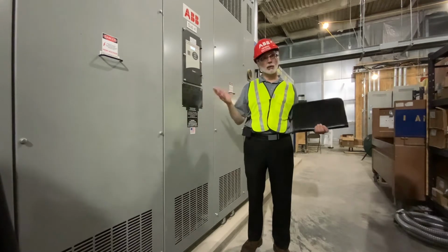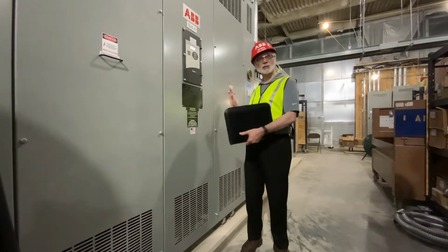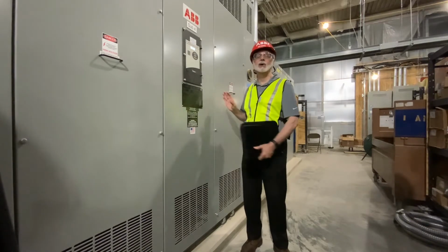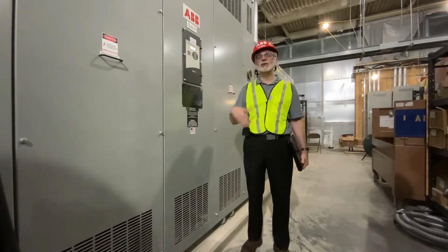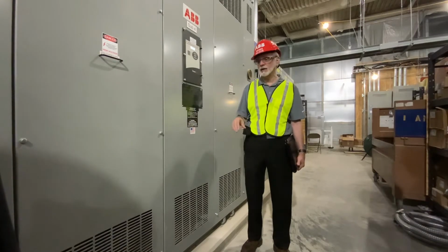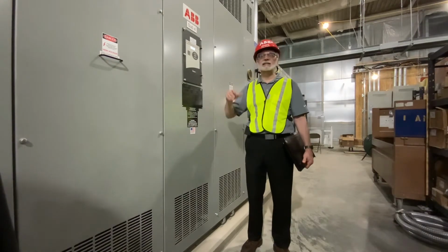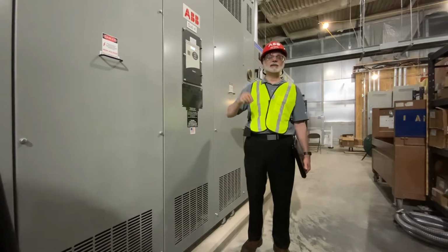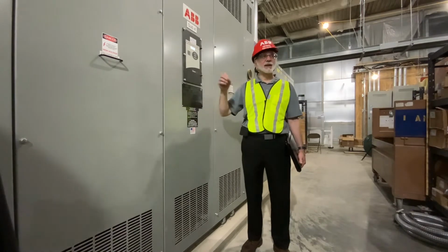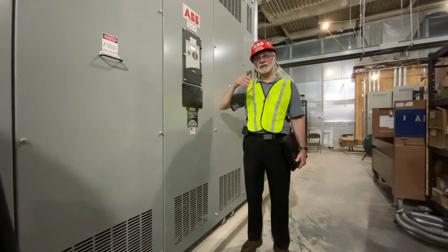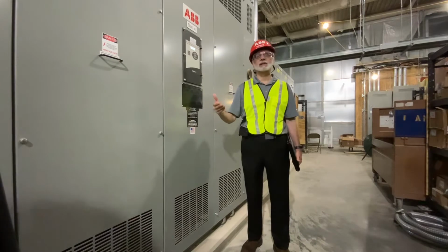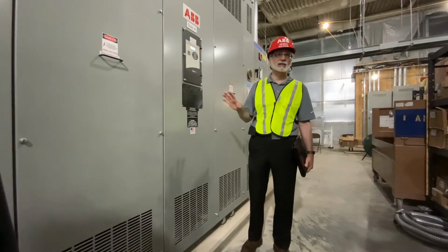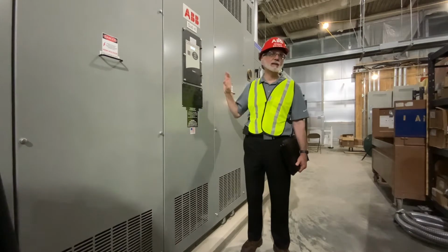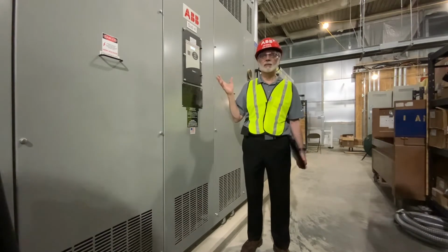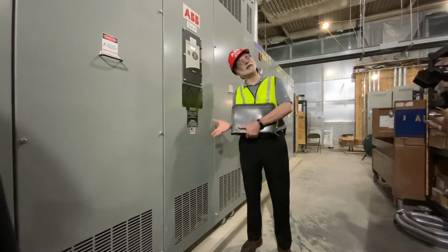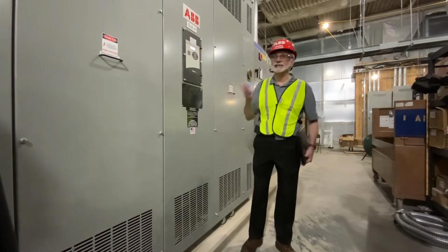Depending on what the critter situation is in the building, this is where critters like to come in the wintertime, okay? So that's another good reason to keep an eye on this piece of equipment, because it doesn't matter if it's a tool, a tail of a critter, or a whole critter, equipment doesn't like phase-to-phase faults, okay? Of all the equipment we're going to talk about today, this is the one you really want to keep the cleanest and look at the most. But the nice thing is this is also the simplest piece of equipment, so it's kind of a win-win.